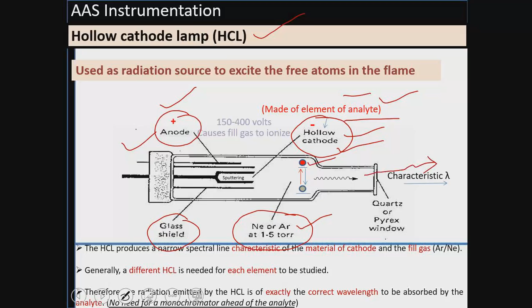This airtight lamp is filled with inert gas, either neon or argon, and kept at around 1 to 5 torr pressure. The inert gas is ionized as a high voltage potential difference is created between the tungsten anode and the U-shaped cathode. When a voltage is applied between these two, the gas filled inside the tube gets ionized, and after ionization these neon or argon cations get bombarded over the hollow cathode, producing an atomic cloud of the analyte material. Some of the atoms generated here are in excited state, and when these come to ground state, the characteristic radiation is emitted.